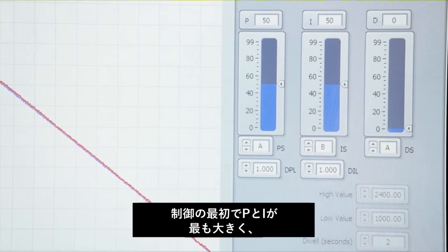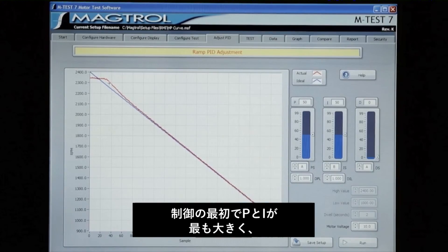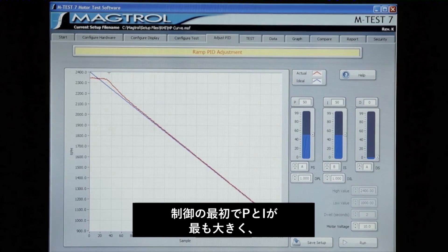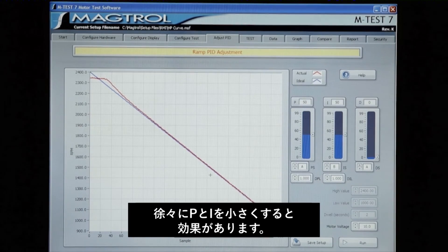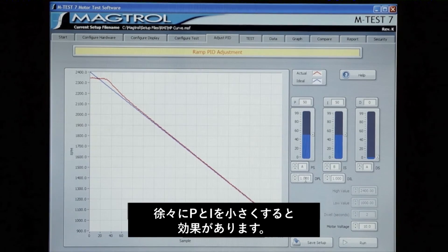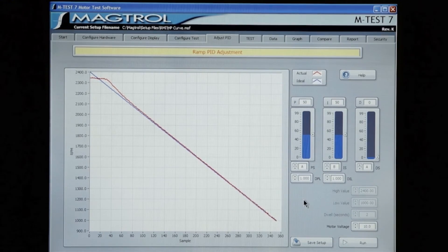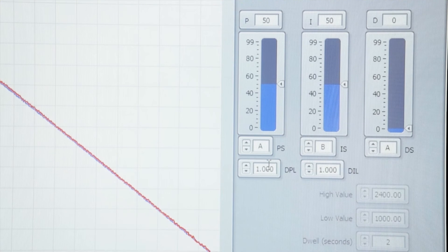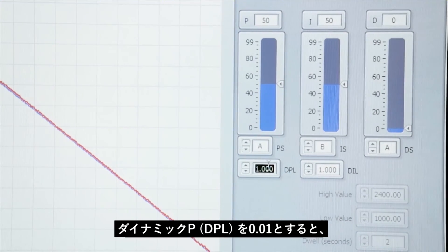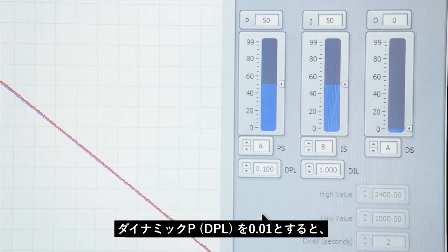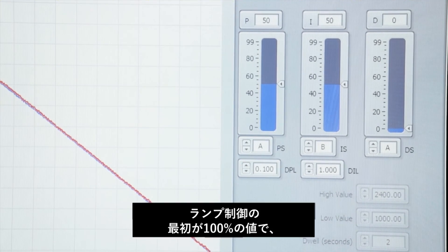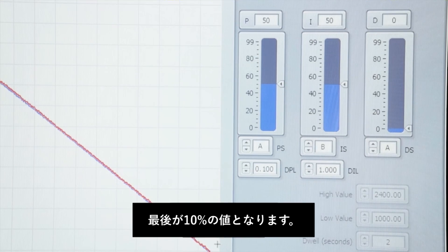The value of the P and the I terms will be the greatest at the start of the ramp and will be reduced to the smaller value at the end of the ramp. Putting a value of 0.1 in for the control causes 100% at the beginning of the ramp and 10% of the value at the end of the ramp.